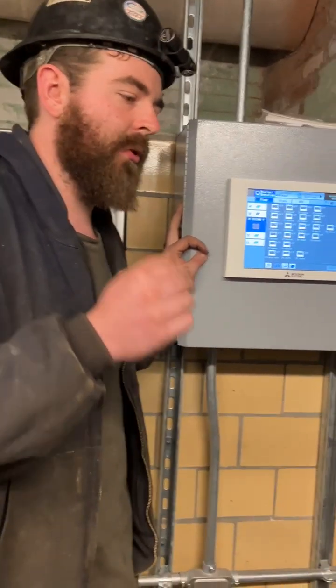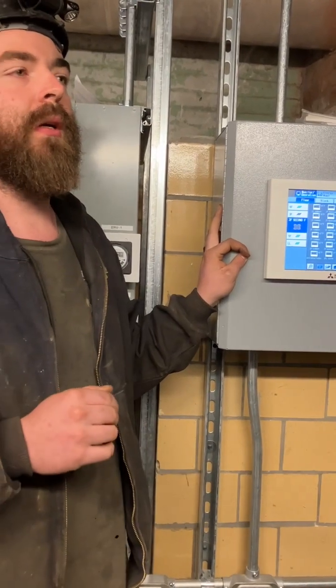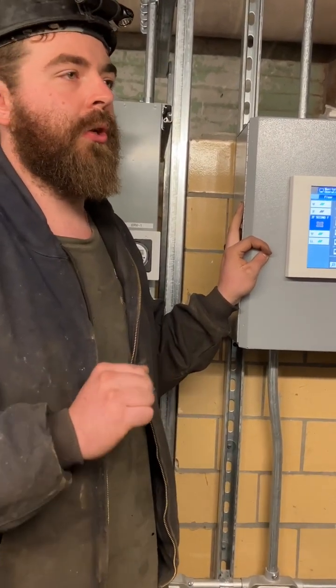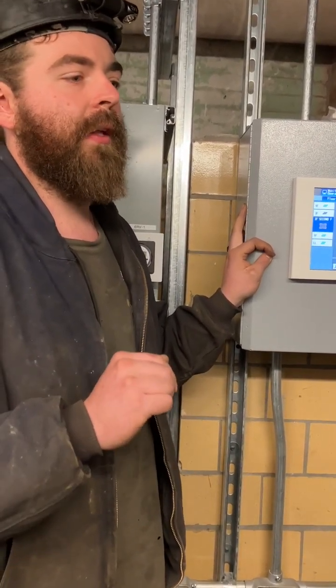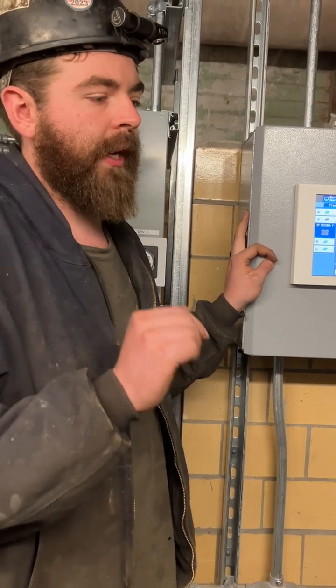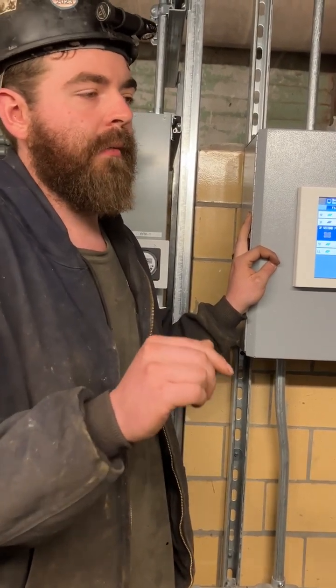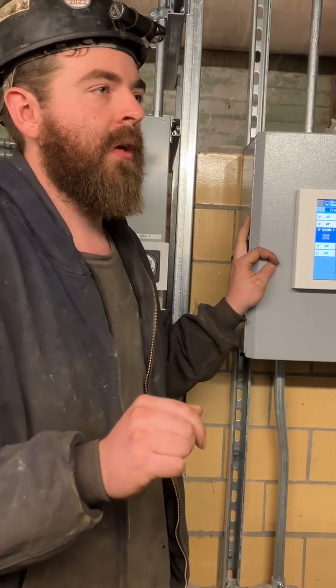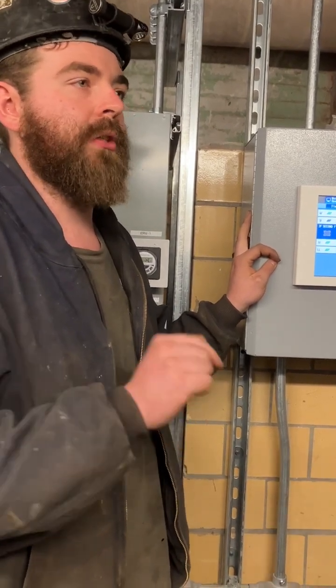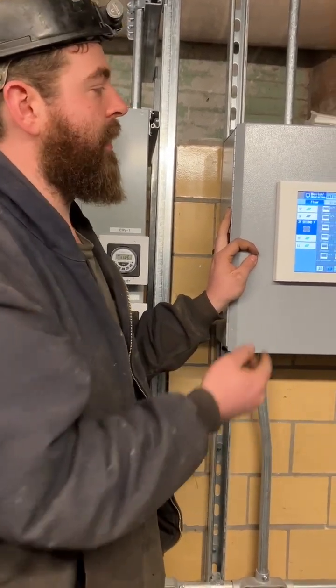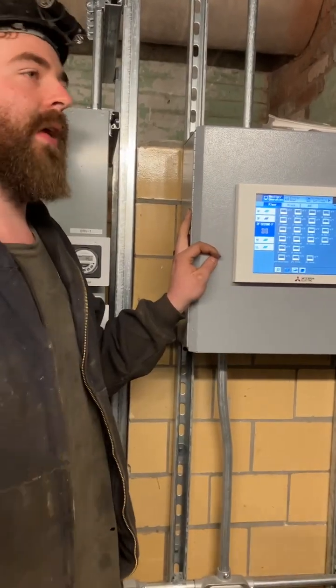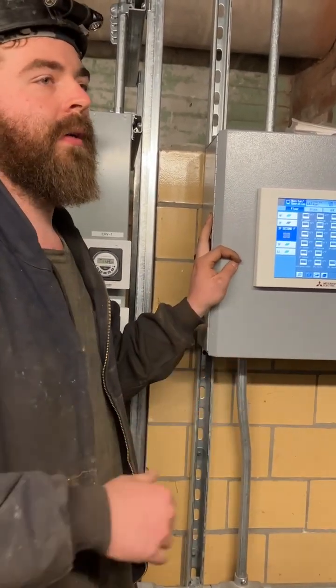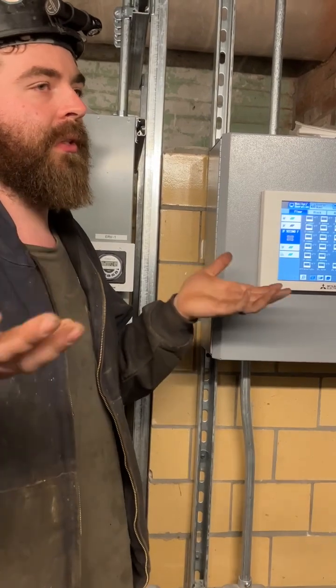That is enabled for having 2 stages of heat and 2 stages of cooling. Stage 1 is baseboard, stage 2 is for the VRF. I think the best thing is to, on the Pelican, take stage 2 and tell the Pelican system stage 2 doesn't exist, or disable stage 2 through the Pelican so it doesn't try to turn this on. Just because if we disable it here, if the Pelican gives it the command, it'll still try to run.